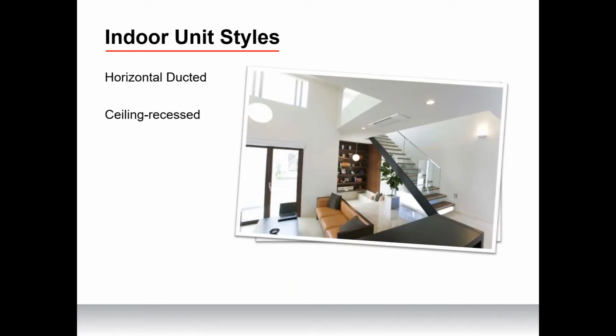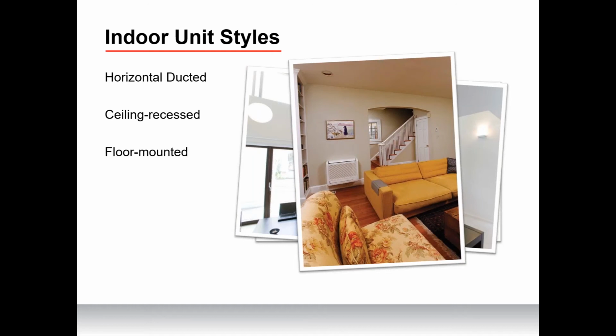And we also have ceiling recessed. Those come in one-way ceiling cassettes that you can see in this picture, and then there's also 4-way ceiling cassette options, but these are ductless units that mount recessed into the ceiling. And there's floor-mounted options as well. So this is a ductless unit that is mounted low to the wall. So it can go on the floor, but it's mainly mounted as a low wall mount. We use these traditionally in applications where you don't have high wall space. We do it a lot around Chicago, where you think of a Chicago bungalow where they finish that attic space into an additional bedroom, and you just don't have high wall. You've got vaulted ceilings and knee walls. A floor mounted system is perfect where you don't have ceiling height.